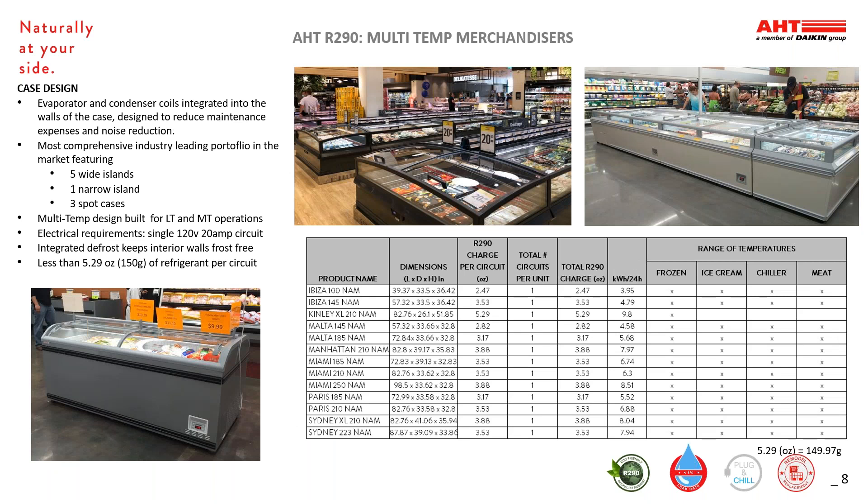Our multi-temp merchandisers are our plug-in refrigeration cases, each using less than 5.3 ounces of R290. These are fully self-contained and only require an electrical connection. These are designed with the evaporator and condenser coils integrated into the walls of the case. This design reduces maintenance expense and reduces noise. All of our multi-temp case models come with three temperature settings: ice cream, frozen food, and medium temperature. Cases also come with an integrated defrost feature that keeps the interior walls free of frost and ice buildup. Our portfolio of multi-temp bunkers is the most comprehensive in the industry. We carry five wide island models along with a narrow island and three spot models.